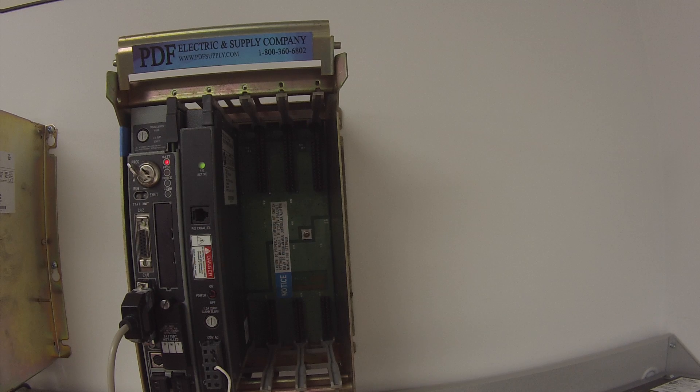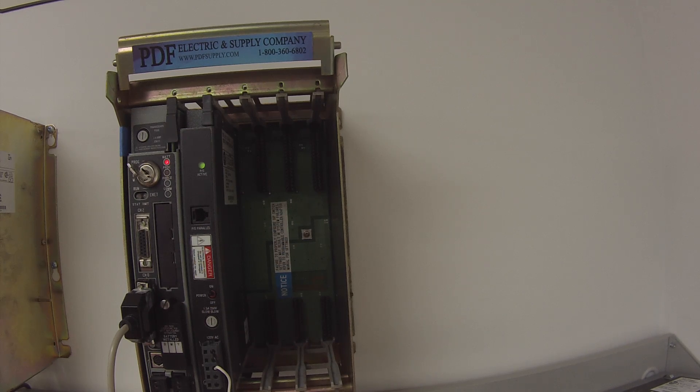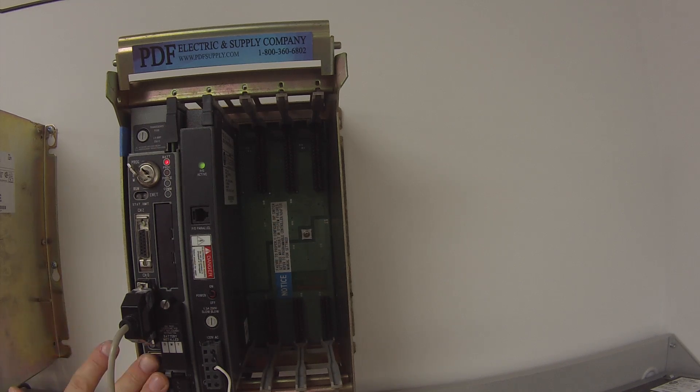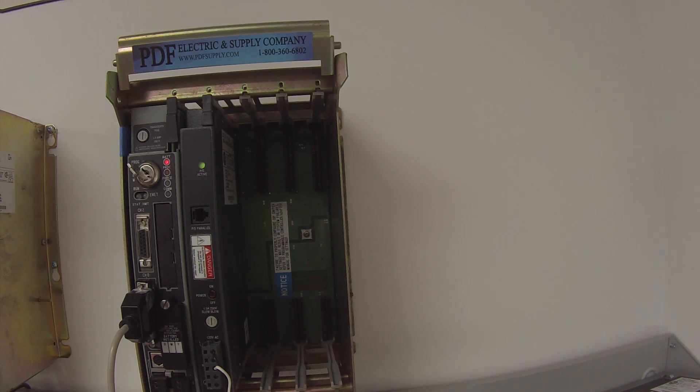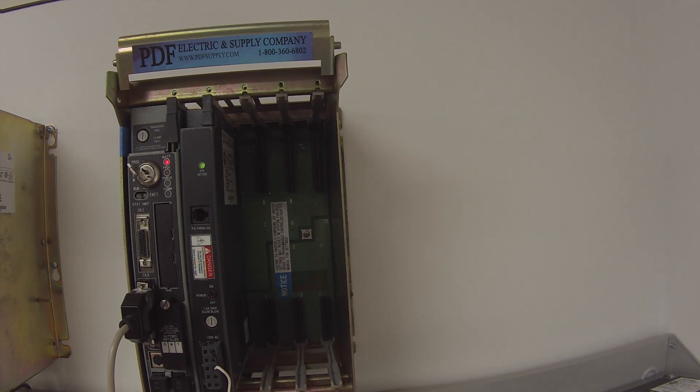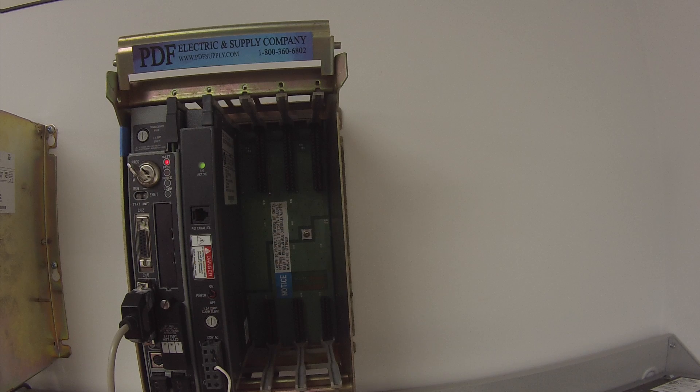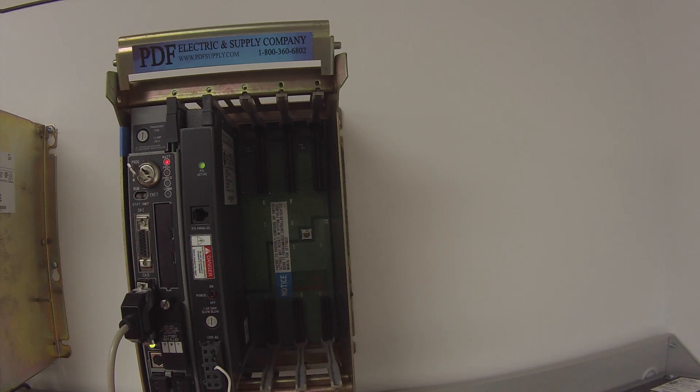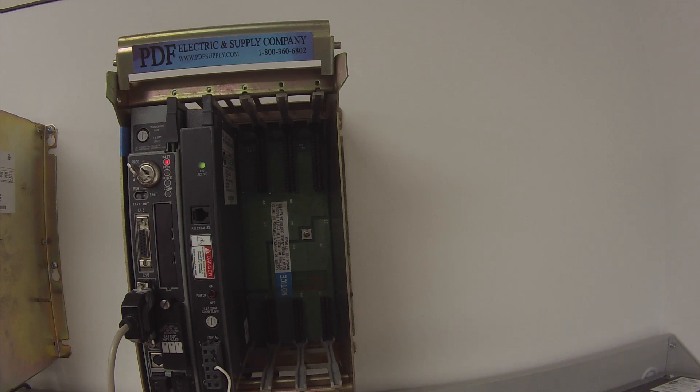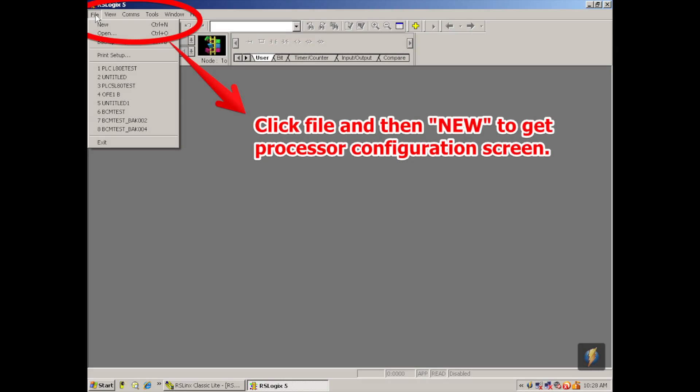This cheat button goes through and it will sort out the baud rate, parity, stop bits, station number, that sort of thing if you don't already have it set properly based on the settings of the processor. Once you're connected, it will say Auto Configuration Successful. I've got that now, so I'm going to hit OK and I'm going to close out my Configure Drivers window and keep RSLinx open, but I'm going to reduce it so it's out of our way and make room for RSLogix 5.